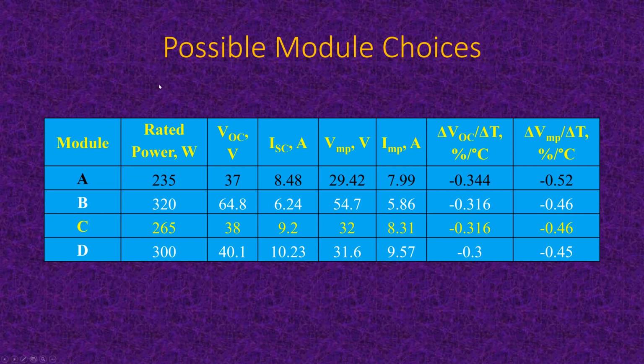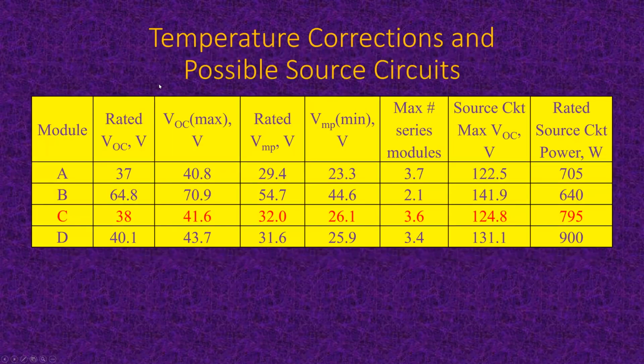Okay, so here we've got some module choices. Fine, we choose one, do temperature corrections, and you use the temperature coefficients. As they get colder, their voltages go higher, their power goes up. So the colder they get, the more power they give. The warmer they get, the less power they have available. Their rated power is at 25 degrees C.